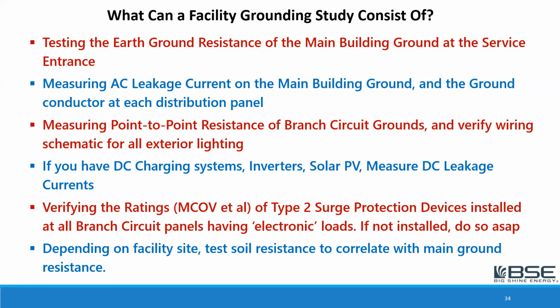So what can a facility grounding study consist of? This is not comprehensive, but it's just to give you an idea. So first, testing the earth ground resistance of the main building ground at the service entrance. That's sort of your benchmark. Also, we like to measure AC leakage current on the main building ground and also on the ground conductor at each distribution panel, because there is normally a little bit of what we call leakage current, because the wires throughout the building have voltage on them, and there's a little bit of capacitive and inductive coupling or connection, you could say, between them.